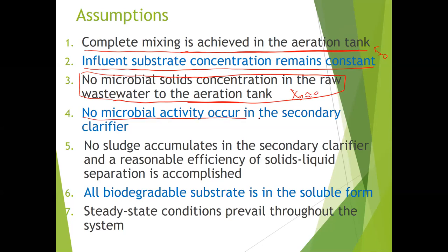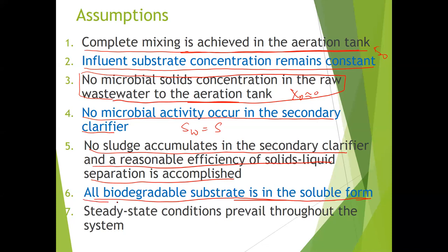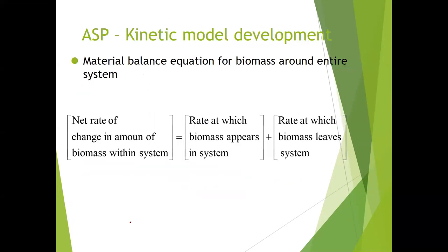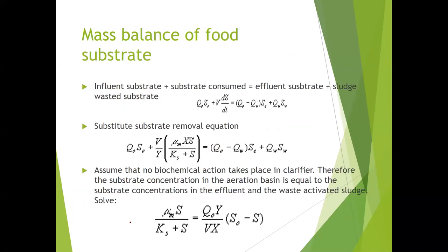No microbial activity occurs in the secondary clarifier. It means that SW is equal to S. No sludge accumulates in the secondary clarifier, and a reasonable efficiency of solid-liquid separation is accomplished. All biodegradable substrate is in the soluble form. So the substrate which is coming in, S naught, must be in the soluble form, and then steady state conditions prevail, meaning when we make the mass balance.